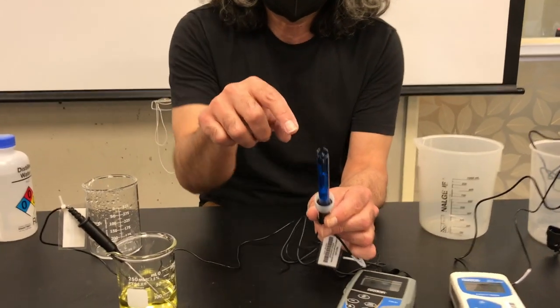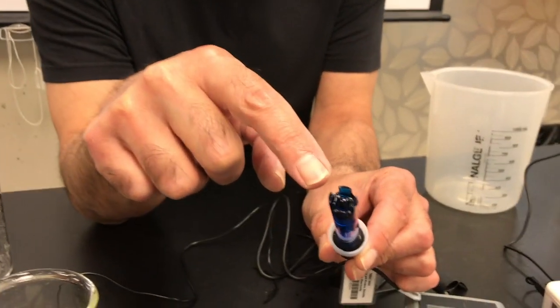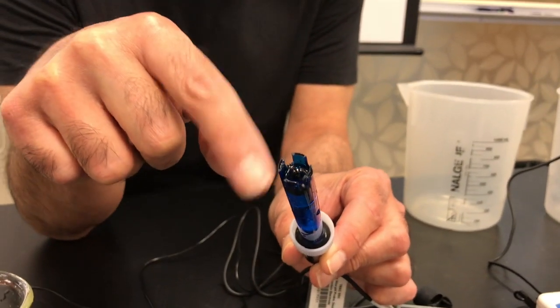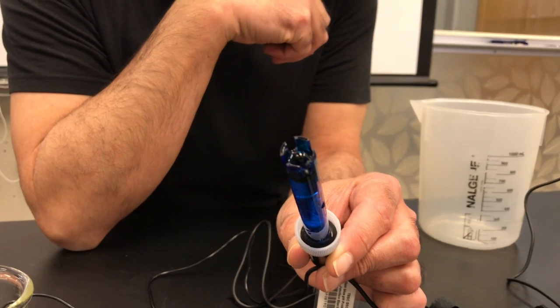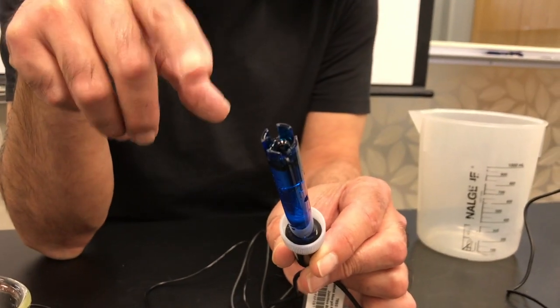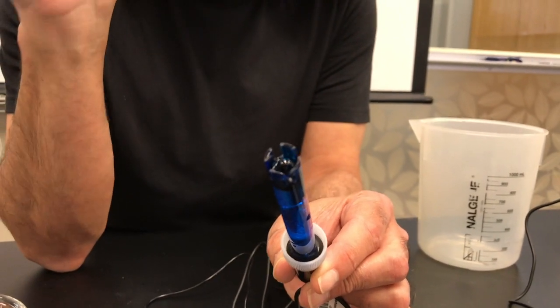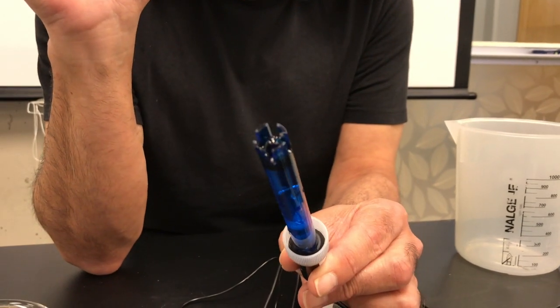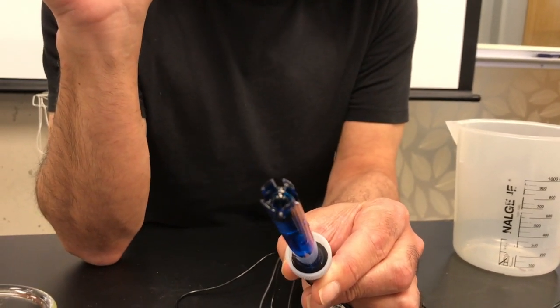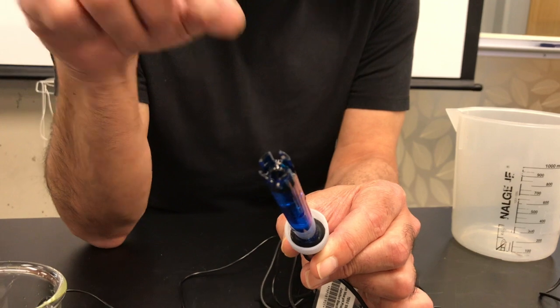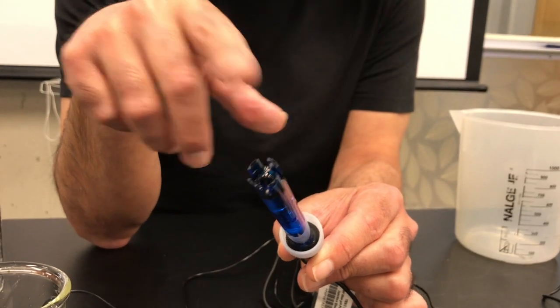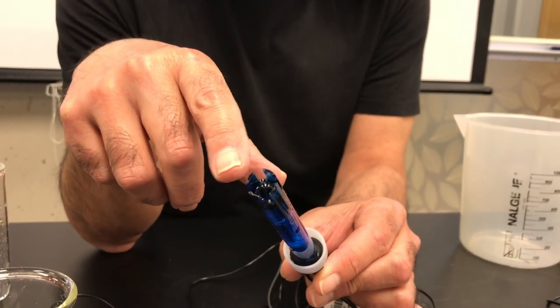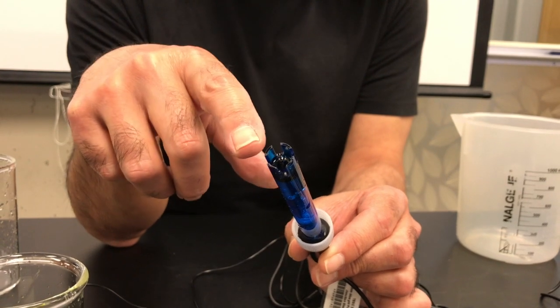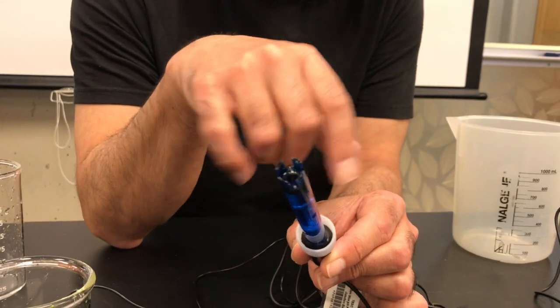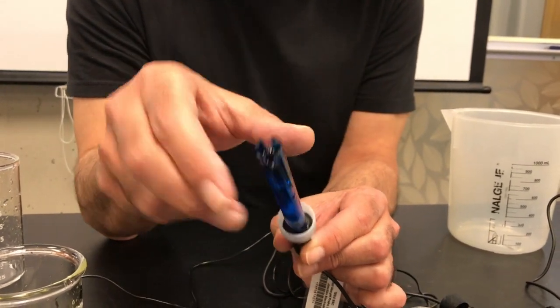And the only thing that is not made of plastic is the actual membrane. The membrane is a little glass bulb at the very end of the probe, and you need to be aware that it's glass because it's very, very thin glass and it's very fragile, okay? So be careful when you're taking your pH measurements that you don't hit the glass membrane against your beaker, for example, and break the glass.